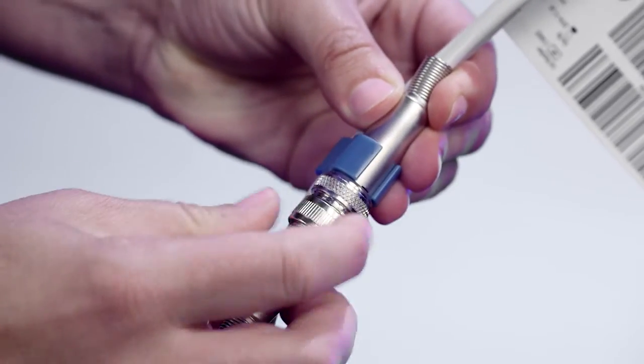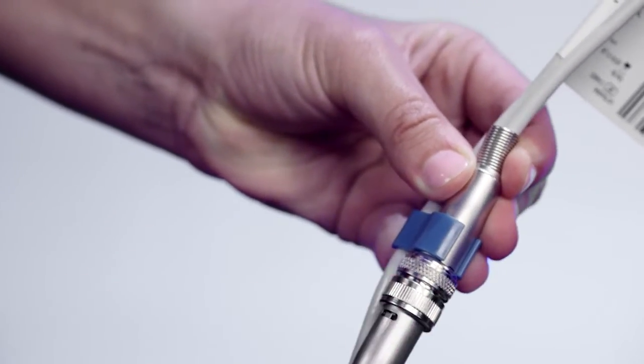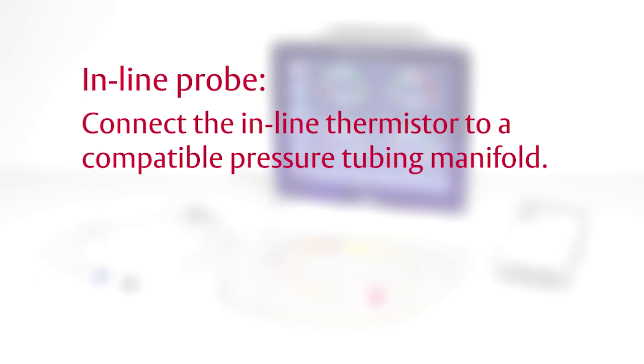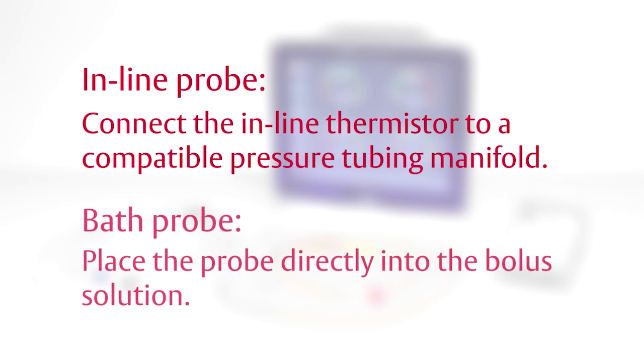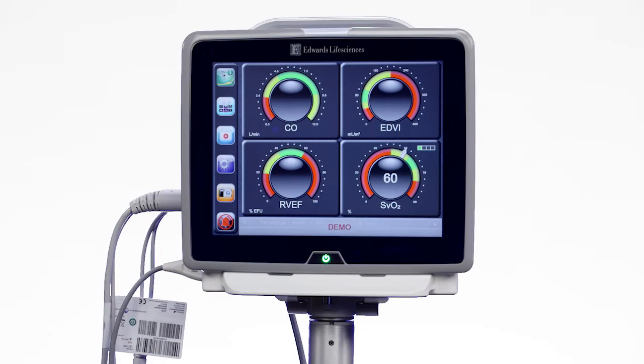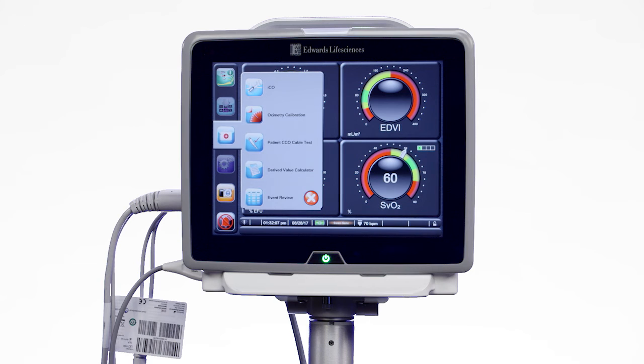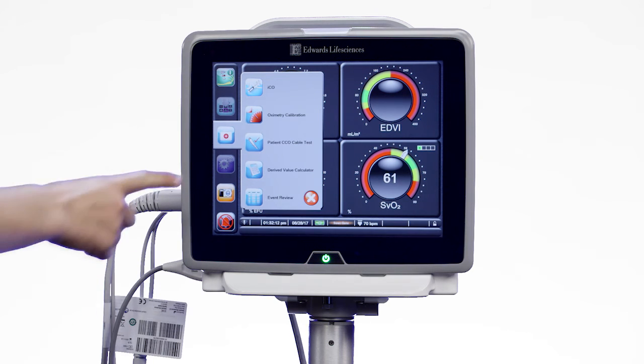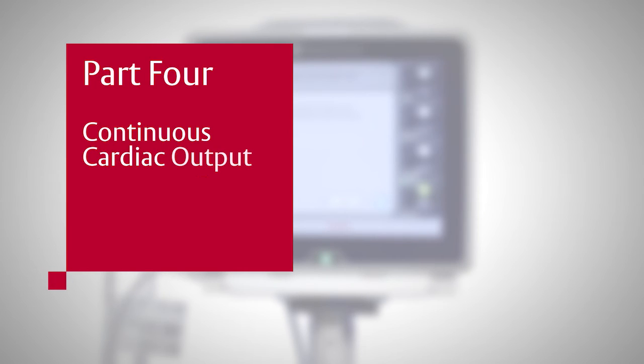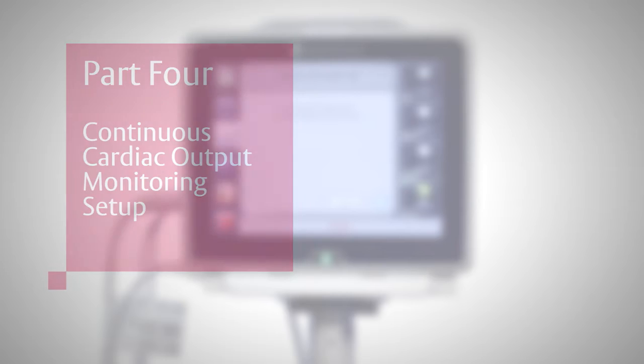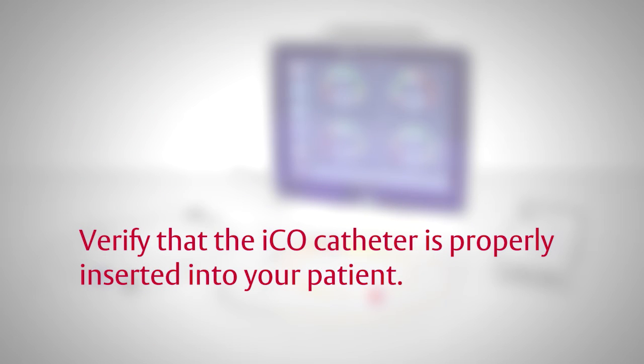Connect the injectate temperature probe, inline or bath, to the silver connector of the patient CCO cable. If using an inline probe, connect the inline thermistor to a compatible pressure tubing manifold. If using a bath probe, place the probe directly into the bolus solution. To check the integrity of the CCO cable, you may perform a CCO cable check by following the procedure described in Part 4, Continuous Cardiac Output Monitoring Setup. Verify that the ICO catheter is properly inserted into your patient.